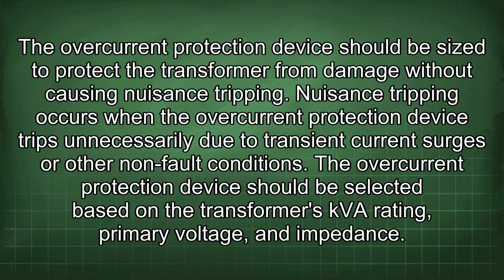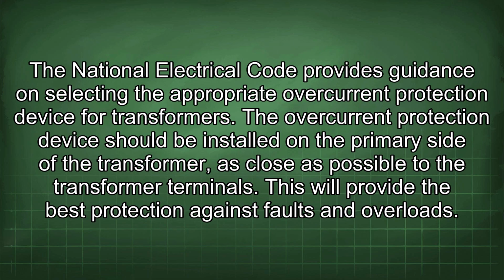The overcurrent protection device should be selected based on the transformer's kVA rating, primary voltage, and impedance. The National Electrical Code provides guidance on selecting the appropriate overcurrent protection device for transformers. The overcurrent protection device should be installed on the primary side of the transformer as close as possible to the transformer terminals. This will provide the best protection against faults and overloads.